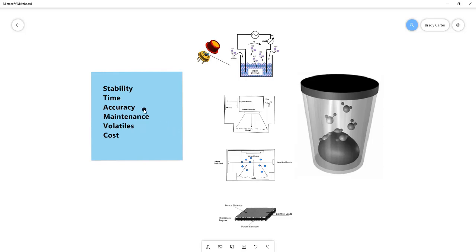So with all conditions the same, the chilled mirror and the TDL will be slightly faster than the other two methods. In terms of accuracy and precision, which both need to be considered, the highest level of accuracy reported is for the chilled mirror or dew point sensor or method, as well as the electrolytic method at 0.003, followed by the TDL at 0.005, and then the capacitance usually around 0.01.